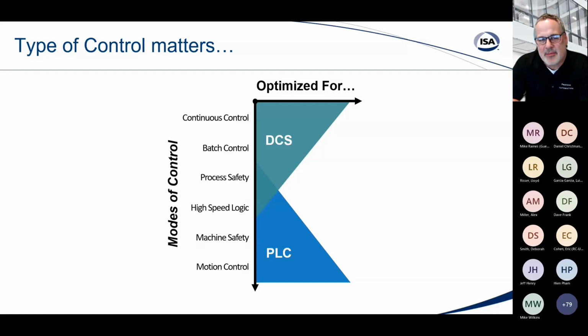And I talked about the optimization. So if you look at this chart here, where we're looking at where the DCS is really optimized for versus the PLC, the different modes of control. When you're looking at strictly continuous control, batch control, process safety, it's more inherent to the DCS. Then you start getting that overlap with the high-speed logic on the PLC, the machine safety, and the motion control.